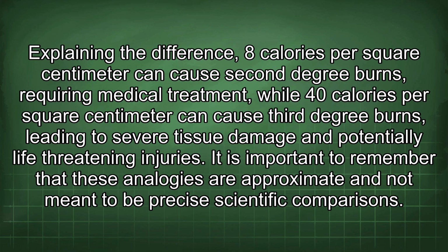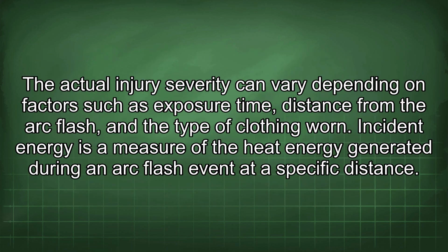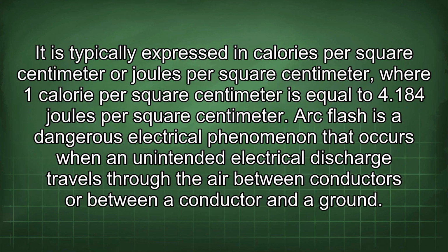It is important to remember that these analogies are approximate and not meant to be precise scientific comparisons. The actual injury severity can vary depending on factors such as exposure time, distance from the arc flash, and the type of clothing worn. Incident energy is a measure of the heat energy generated during an arc flash event at a specific distance. It is typically expressed in calories per square centimeter or joules per square centimeter, where 1 calorie per square centimeter is equal to 4.184 joules per square centimeter.